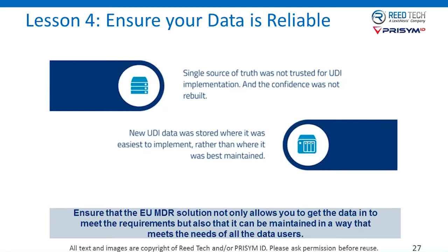In many cases, some of our clients valued the ability to do a pre-check before it was actually submitted to the agency. So going through multiple iterations of the data set and the records, so we're talking about numerous fields, 55 fields along with the device identifier that need to be collected for each device. The other thing that came up was that there was some confusion about applying the device identifiers to each of the various products and packaging, so it wasn't as easy and clear as originally thought, and I think you mentioned that in your particular case as well, Chris.